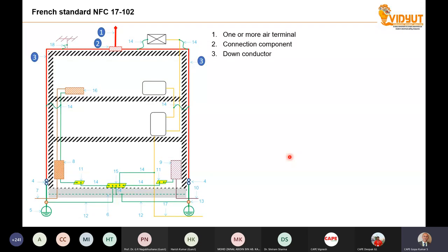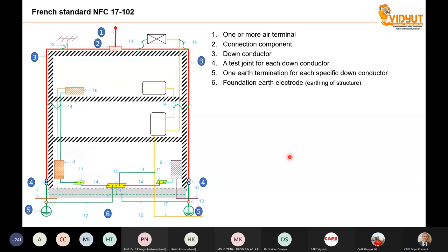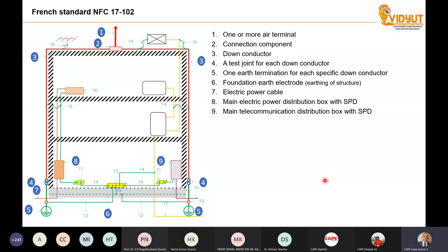Remember, there are two down conductors, whereas in India we always talk about one down conductor, test joints, earth electrodes, foundation earth electrode. Foundation earth in the sense the earth electrode is connected back to the foundation of this particular building. Then you have the electric power cables coming inside. You have the electric power distribution board. You have the telecommunication power distribution board. You have one or more equipotential bonding bars. If you look at this picture very carefully, the down conductor is also connected to the bus bar. The down conductor is also connected to the earthing of this electrical appliance. The down conductor is also connected to other parts. The down conductor is also connected to some electrical appliance at the top.